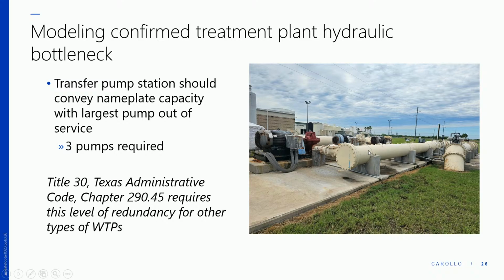Now, the Texas Administrative Code for any other type of water treatment plant says that you need to be able to convey all of that capacity with one pump out of service. So this is something we recommend. When I say any other type of water treatment plant, I mean surface water treatment plants or groundwater treatment plants that are under the direct influence of surface water.